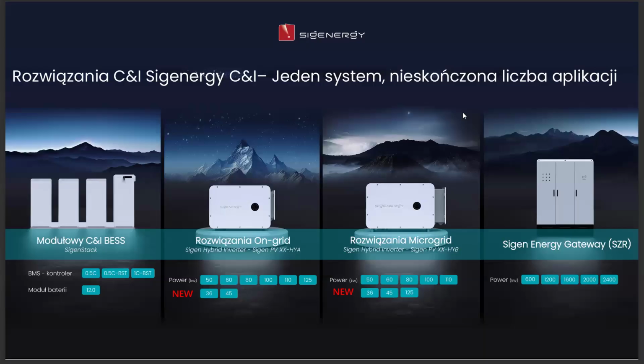A typical market scenario is to obtain 100 kilowatts of power. With a 0.5C system, the customer must buy 200 kilowatt-hours of storage. With our 1C capability, to obtain 100 kilowatts of power, we install 100 kilowatt-hours of storage. What does that mean? 50% fewer batteries. 50% less installation space. Significantly lower capex. No artificial oversizing of the system. In this area, we can confidently say that we offer one of the most cost-efficient solutions currently available on the market. Key value for installers and advisors.